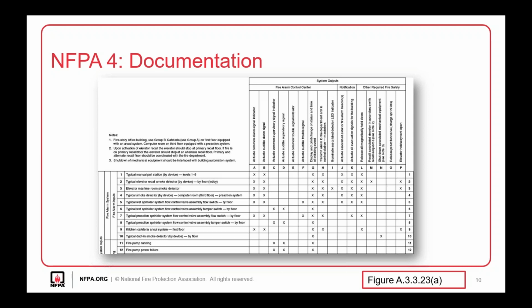So once the testing is completed and the documentation is given to the owner by the integrated testing agent, it needs to be retained by the owner and/or the owner's representative, and the location of the documentation must be shown on the fire alarm control panel. And then the owner is responsible for maintaining the last 2 integrated system tests.